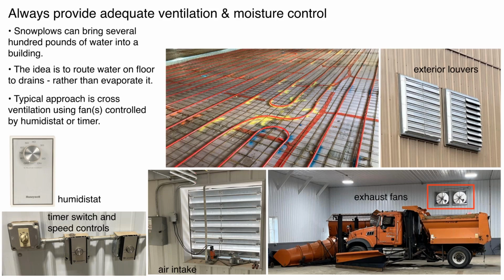One of the ways to deal with this is cross ventilation. And in this particular garage, this is the air intake. It's a large louvered panel with a motorized damper on it. And you'll see over here above the truck, a couple of fans. These fans in this particular building are just controlled by a timer, and there are speed controls on them so they can vary the speed of the motors.